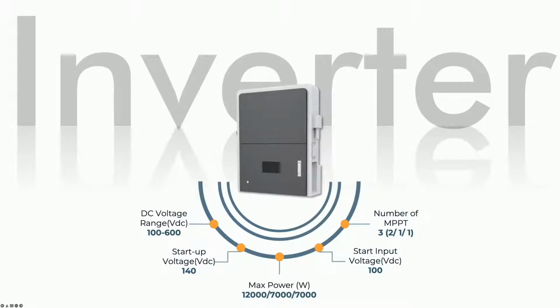If the solar panels, the PV, are generating more power than the load consumption, the excess solar power will be stored in the battery. When solar power exceeds the sum of the load power and max battery charging power, for example when the battery is nearly full, the LXP hybrid inverter will signal the grid interactive inverter to reduce power via the frequency shifting power reduction mechanism, thus maintaining the balance of generation and consumption of the microgrid system.